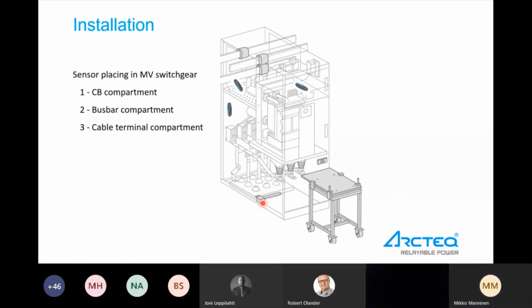And so, one sensor for the cable compartment at the very best location. This is not the best location, but it is an example. One for the bus bar and one for the circuit breaker. And for the circuit breaker, it is best to have it in the location which sees the connection parts at best, and then keep the cable away from the moving elements or any withdrawable breaker moving elements. So that is quite important to keep in mind.